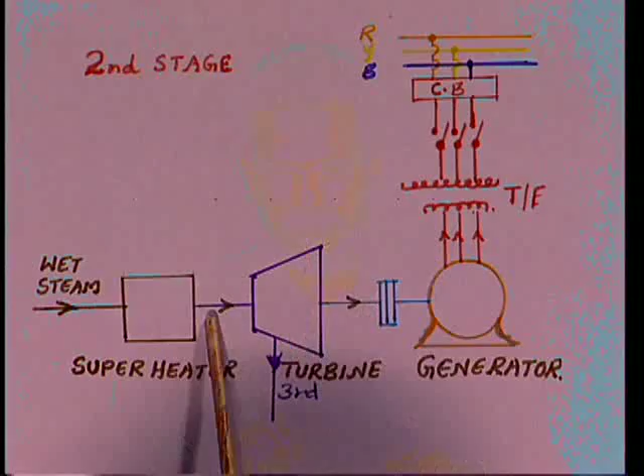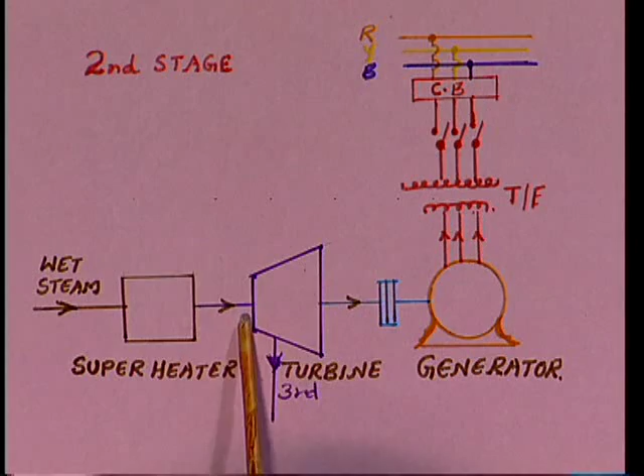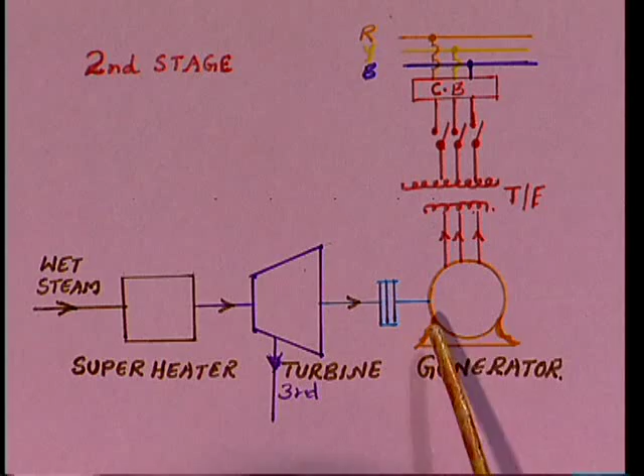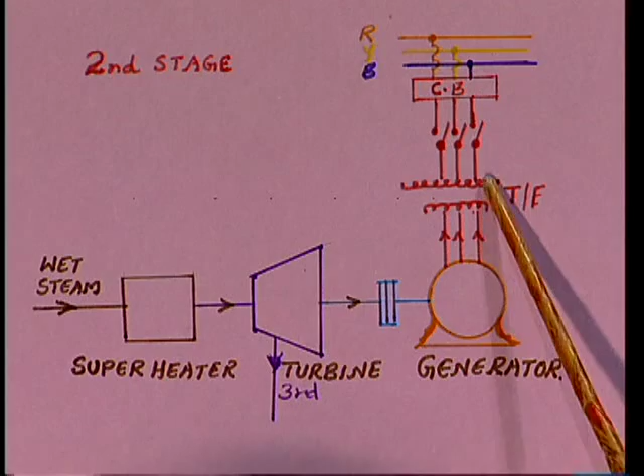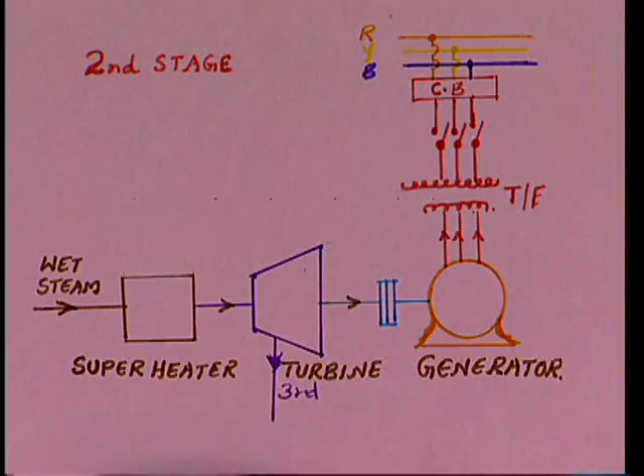Why do we need only hot steam? Because if we allow wet steam into the turbine blades, the turbine blades will get rusted and the efficiency will decrease. So therefore, to increase the turbine efficiency and to avoid corrosion of the blades, dry steam is fed to the turbine blades. In the turbine, the steam energy is converted into mechanical energy. That mechanical energy is transferred to the generator through the coupling system, where the electrical energy is produced and given to the transformer through the switch and circuit breaker to the bus bar and various switch yards. This is the second stage of getting the electrical energy.